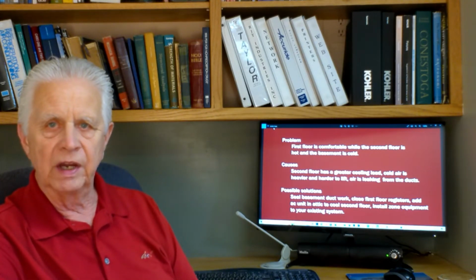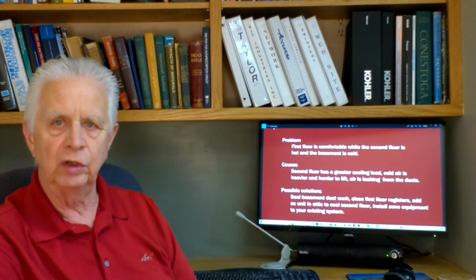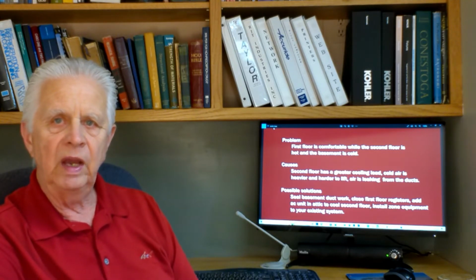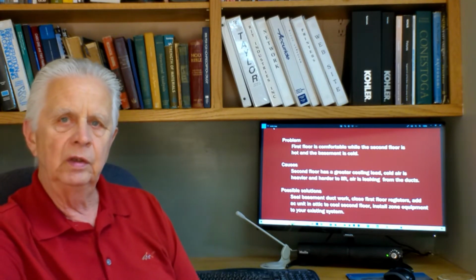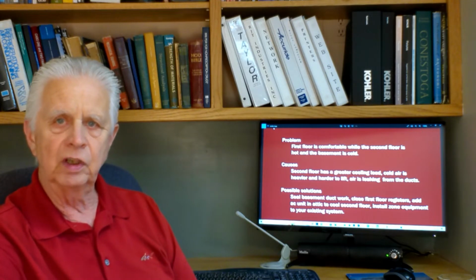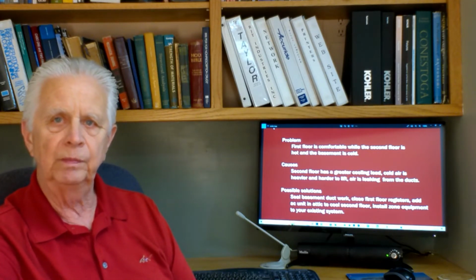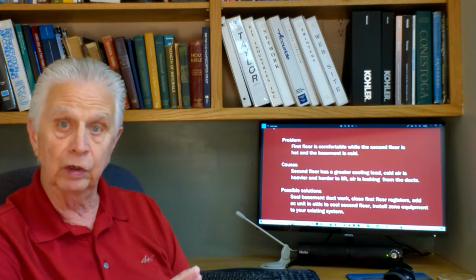There's another way. It's known as zoning. You add a second thermostat on the second floor to sense the temperature there. You add a control board that will take the thermostats, put them together, figure out what to tell the furnace to do, and you add dampers that the control board will control and direct the air where you want it at what time you want it there.